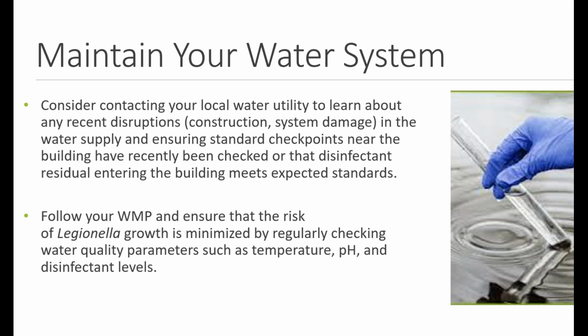So you always want to be prepared for that and knowledgeable on that, and make sure that standard checkpoints near the building—where the water's coming in from outside—have been checked, and that the disinfectant residual, the amount of disinfectant left over after it's been used to kill any bacteria or virus coming in, is the correct amount. If you get some sort of impact or disruption in the system, the normal amount of disinfectant you're using might get all eaten up with additional bacteria and debris entering your system and not have enough to meet the standards to control Legionella.